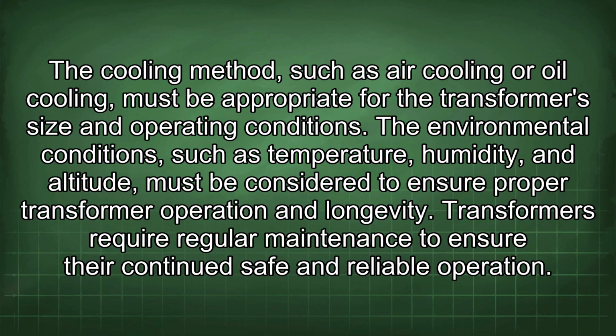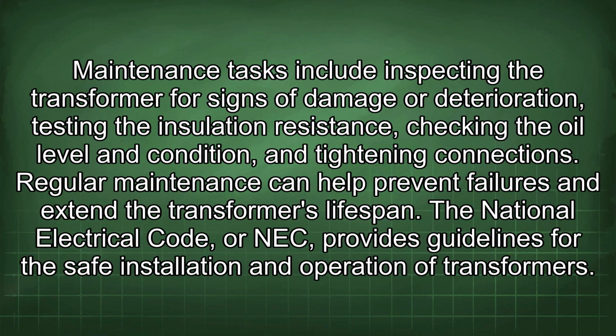Transformers require regular maintenance to ensure their continued safe and reliable operation. Maintenance tasks include inspecting the transformer for signs of damage or deterioration, testing the insulation resistance, checking the oil level and condition, and tightening connections. Regular maintenance can help prevent failures and extend the transformer's lifespan.